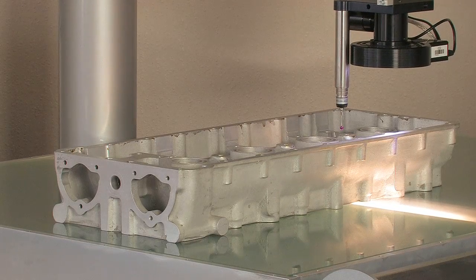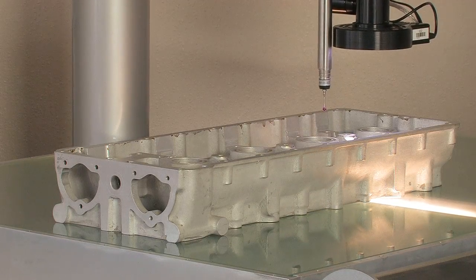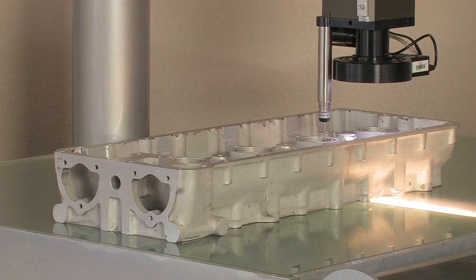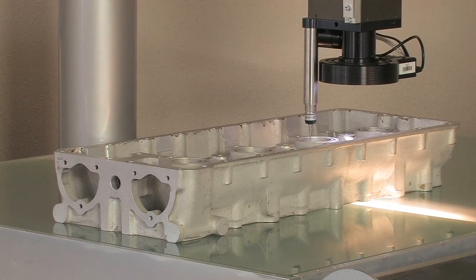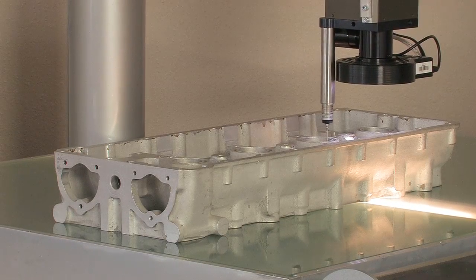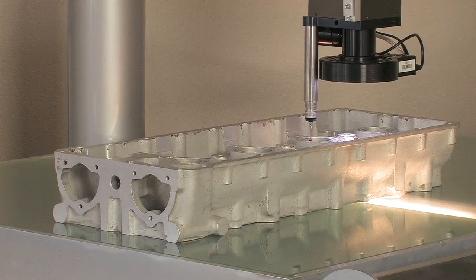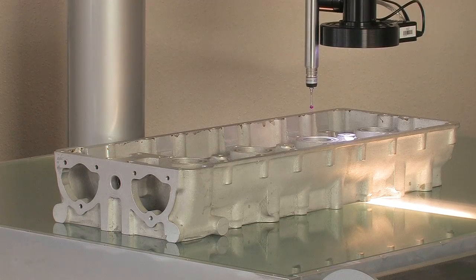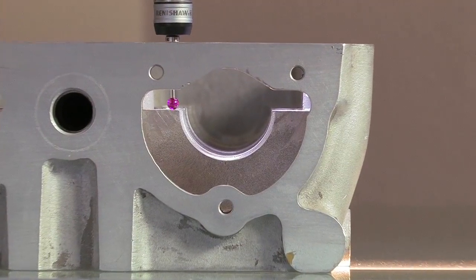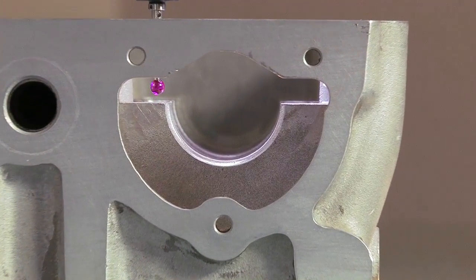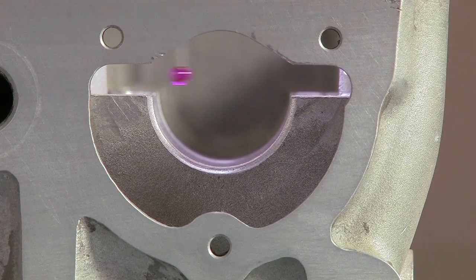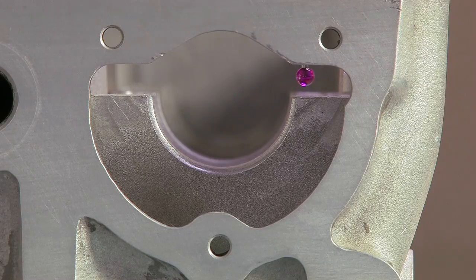Profile lighting, however, is a little different. The patented use of honeycomb material allows the profile light to be transmitted through the 150mm thick machine base. This not only has the effect of collimating the light, but more importantly, the base retains the same mechanical integrity as solid granite.